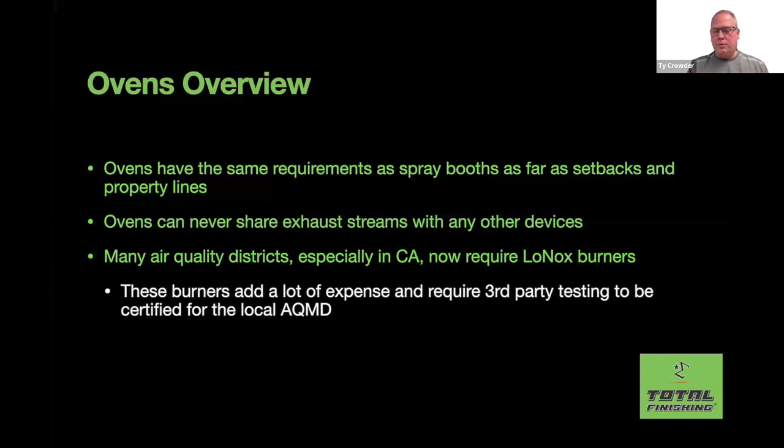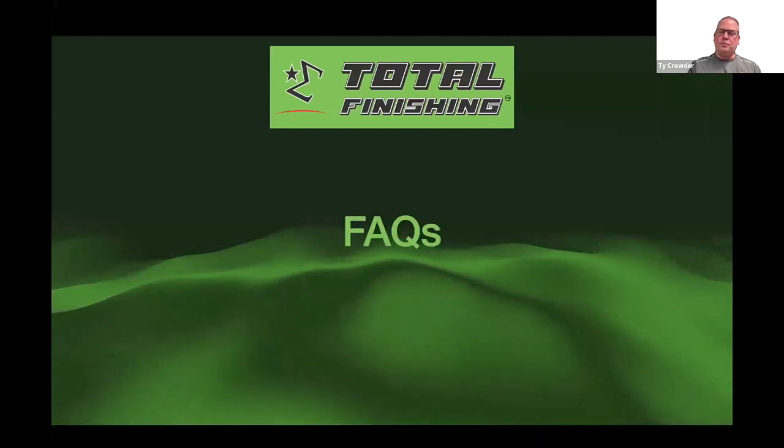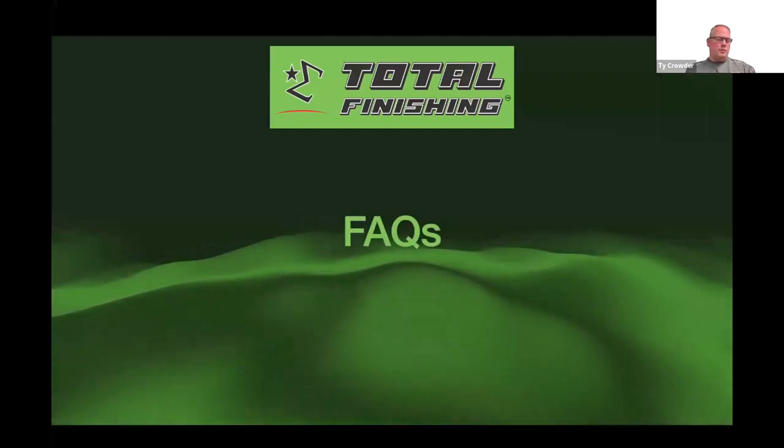Those low NOx burners add a lot of expense, and they also require source testing, or a third party to come out and certify that the customer is indeed using that burner in compliance. That's nothing that we do. That's just something that an AQMD is going to require. Those same low NOx burners are also required on heated air makeups, and they normally have that same third party testing requirement. There are people whose entire business is that. Any questions on ovens?